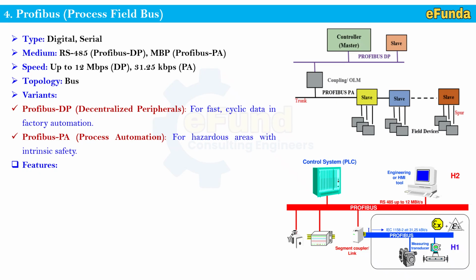In case you need to have control, we use the PLC as per the architecture, and that is connected with a Profibus. And further the engineering or HMI station can handle the data, where RS485 up to 12 megabits per second can handle.